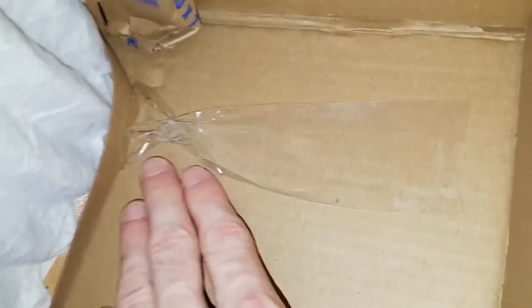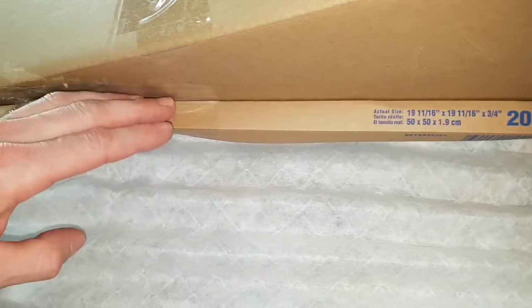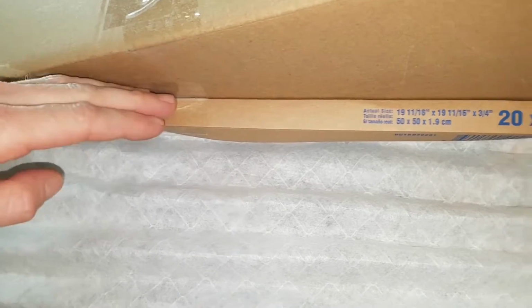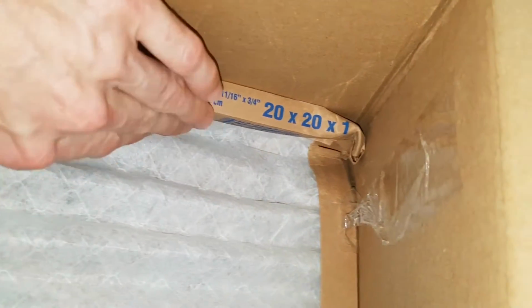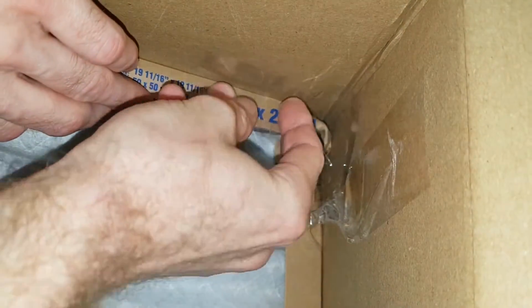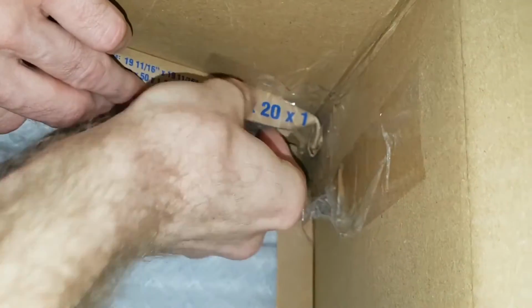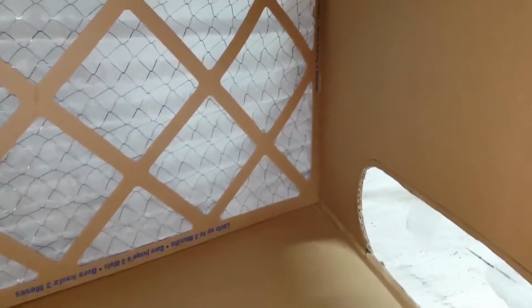It's a small filter, so I think 3 pieces will be enough. A little more tape here and there to seal the gaps. I seal it from this side so that the vacuum from the blower will help hold the tape in place, rather than pull it off. Notice how the right-hand side of the filter, as viewed from this side, is simply wedged into that corner of the box. Seems to secure it okay.